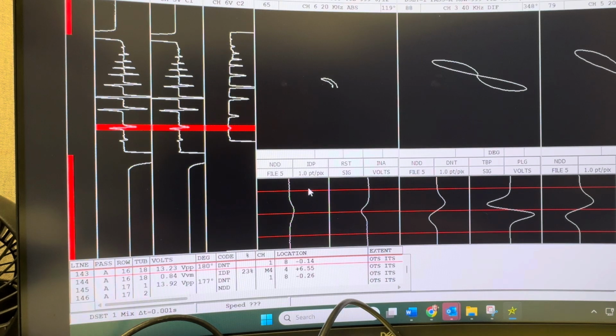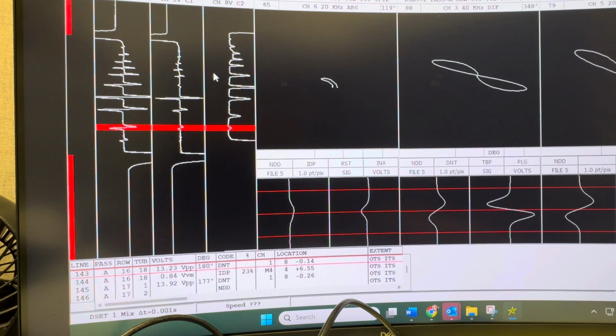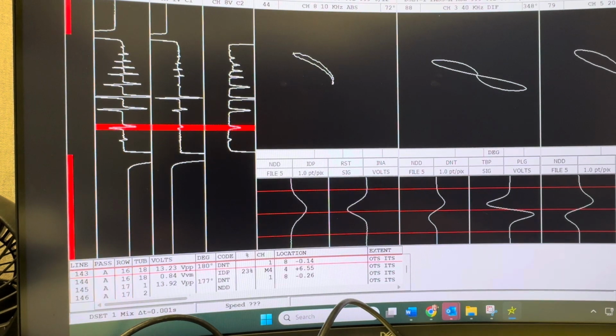But if you're using a probe head like the Delta head from Zetec, that has 3 different coils mounted at the same axial position on the probe head, but separated by 120 degrees. So instead of slewing that data to an axial distance, you're going to slew it by a certain number of degrees. What you do is you'd put coil 1 over here, and then you'd go to coil 2 over here, which might be channel 5 or whatever. And because that's 1/3 of the way around the coil, you would put that channel up in here, and you do the shift middle, and you drag it so that lines up with channel 1.